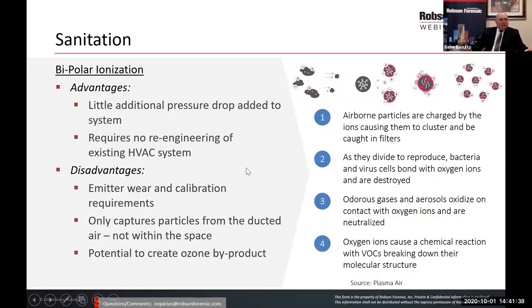All right, the other solution that's out there, although ASHRAE has actually stayed silent in their latest position paper, is bipolar ionization. Bipolar ionization is an electrical and chemical process where it generates ions and charges the air particles with the ions, and those ions plump up the particles and then they are filtered out. There's only a little additional pressure drop added to the system, which is a huge advantage. You're not looking at the energy cost of moving it. It's easily installed. It requires no re-engineering of the existing system. You can plug it into any system.